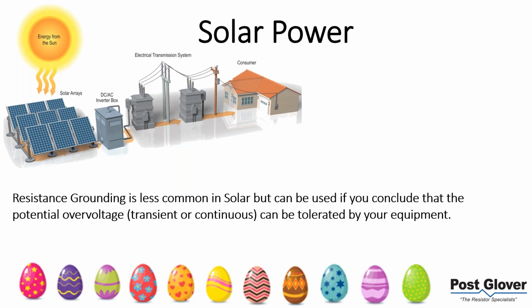I've already mentioned that I'm not going to pretend solar is a common application for this. Based on my research, and maybe others have different opinions, there are potential overvoltages that can be caused by resistance grounding, similar to ungrounded, although not to that extreme. We're not talking about the capacitance kind of runaway overvoltage. We're talking more about the non-faulted phase voltages going up to around line voltage. That's what I'm referring to. So in that scenario, I could see where it might be more complicated to have that resistance ground with your equipment.